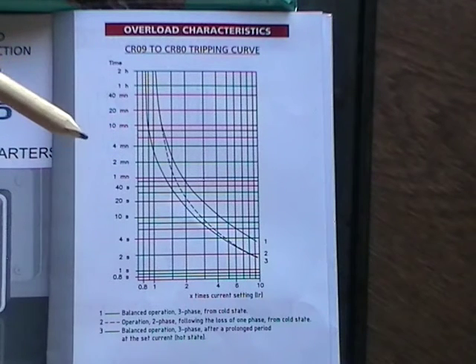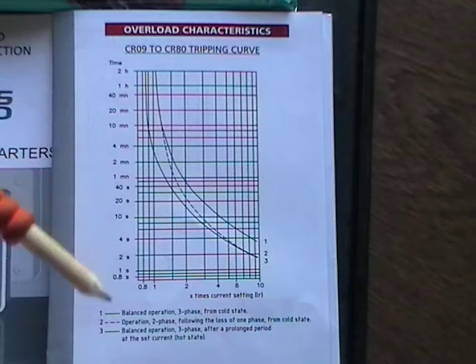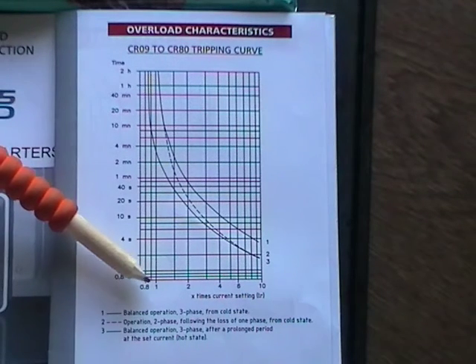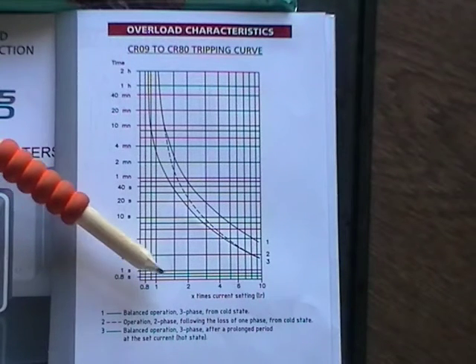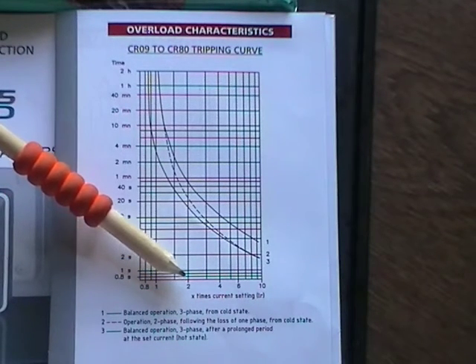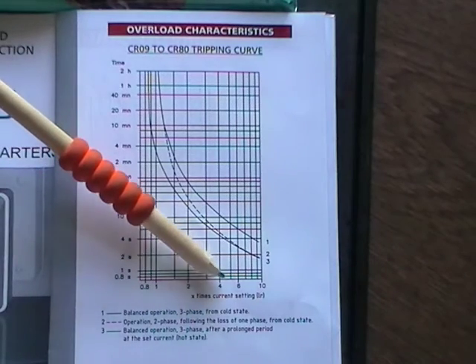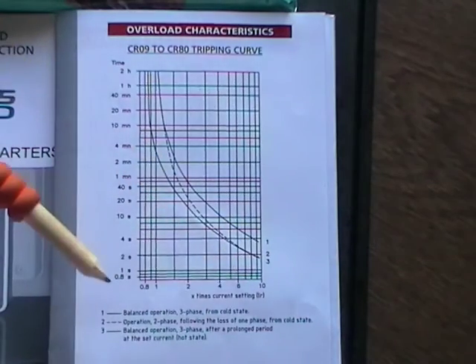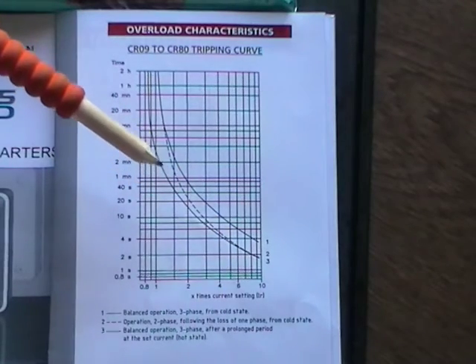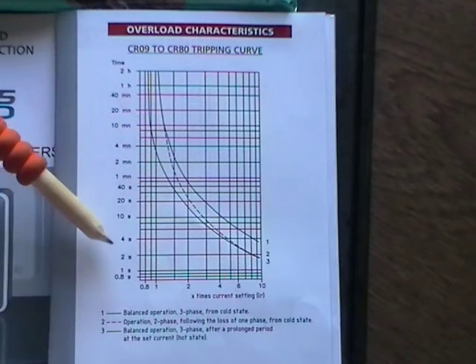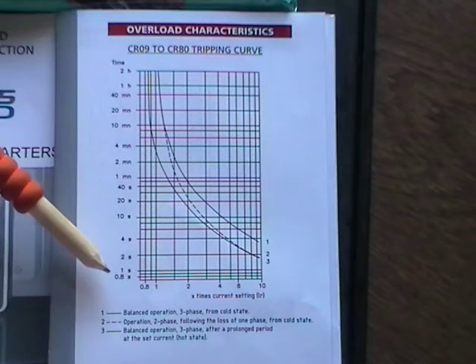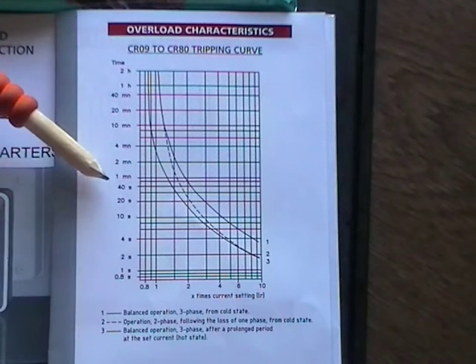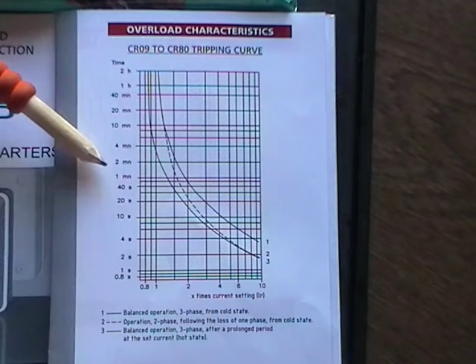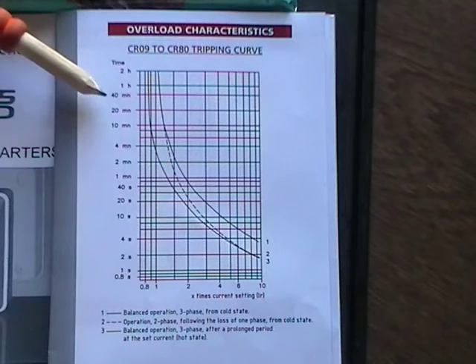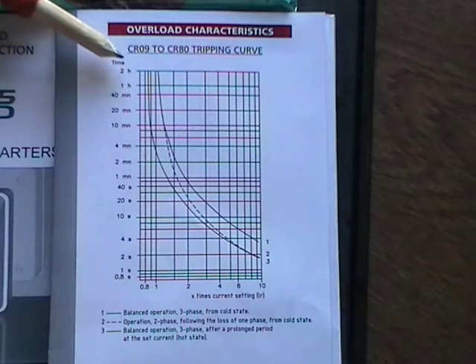The trip can be set, and the chart here shows a number 1 for the actual trip setting. Then we can double the value of the trip setting, or multiply by 4 times, 6 times, 7, 8, 9, 10, and we get a different part of the curve that's then applicable. Up the side we have the time. It starts off in seconds up to a minute, and then we go from there in minutes to 40 minutes, and from there in hours up to 2 hours at the top.